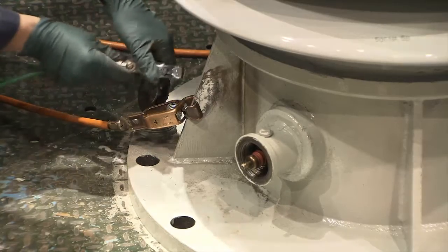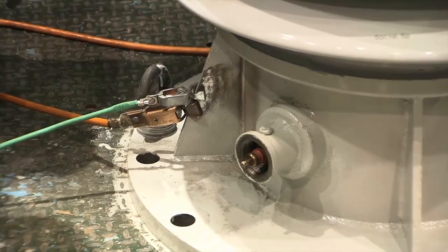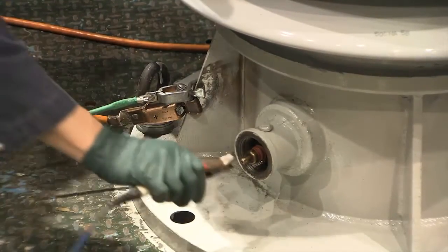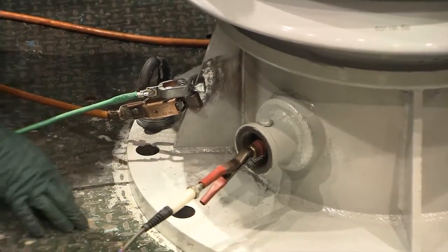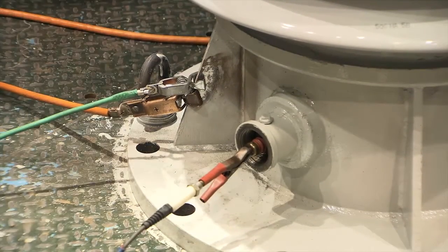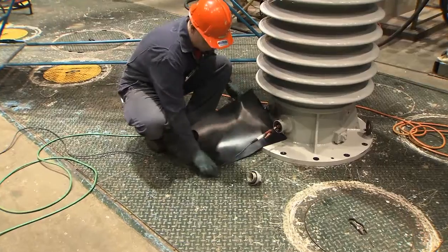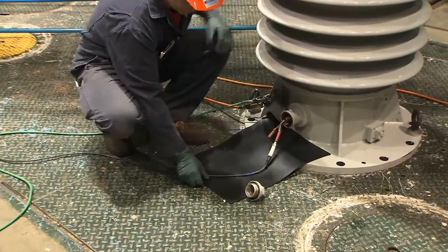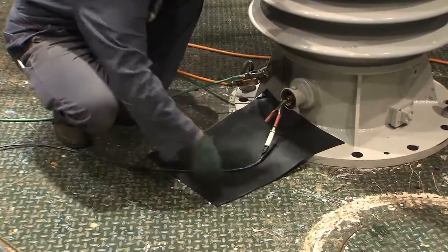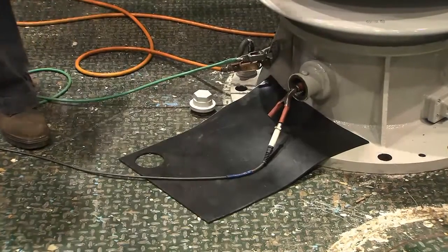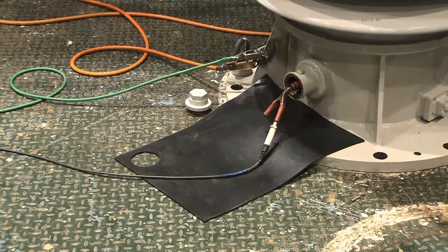Also, connect one end of the ground cable connected to the Biddle test set to the bare metal on the flange. Connect the low voltage lead to the capacitance tap on the flange. Place a rubber mat over a section of the floor and on the flange so that the cable attached to the cap tap rests on the mat.